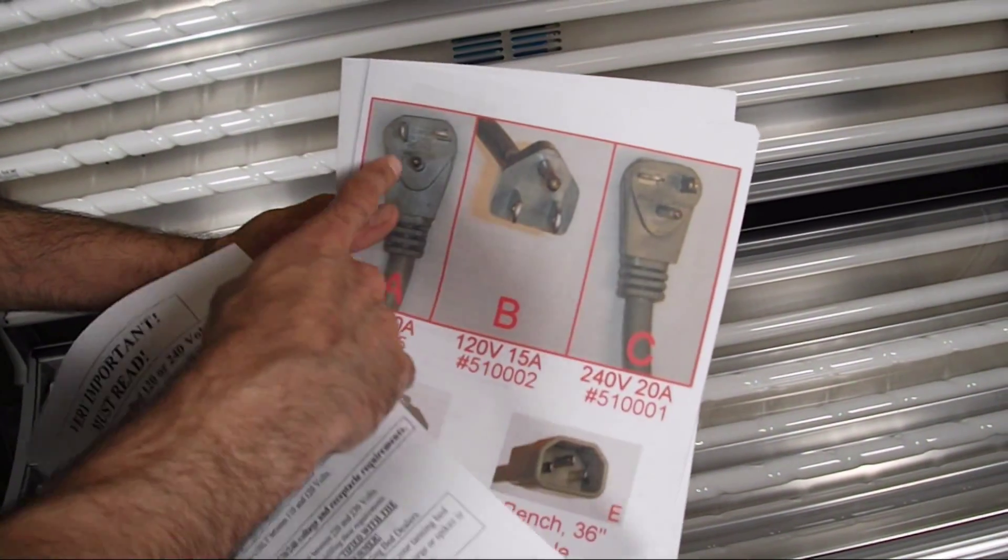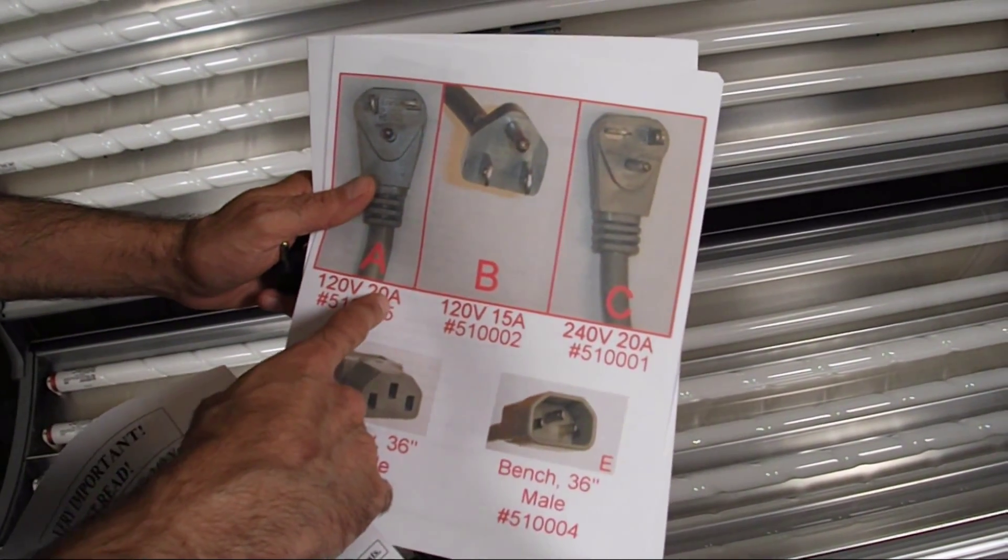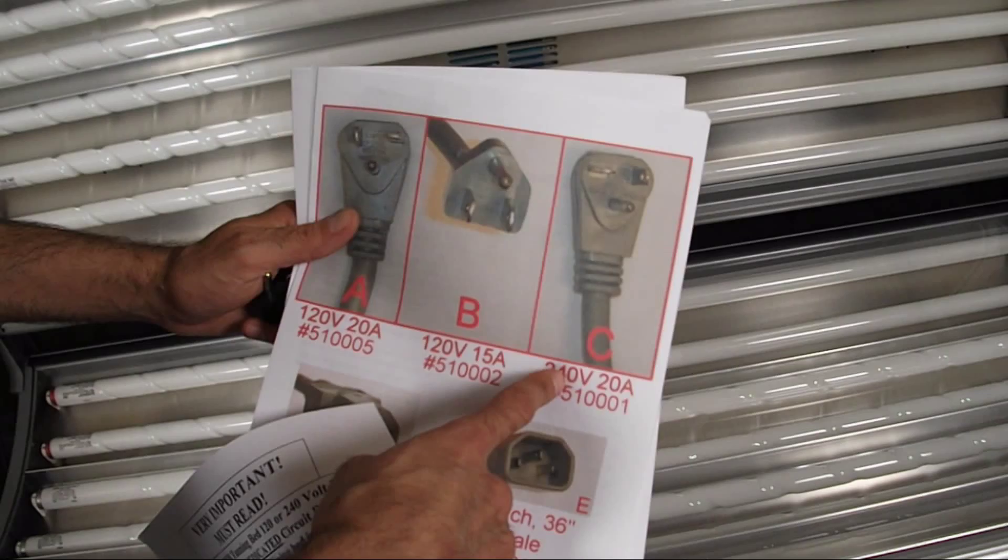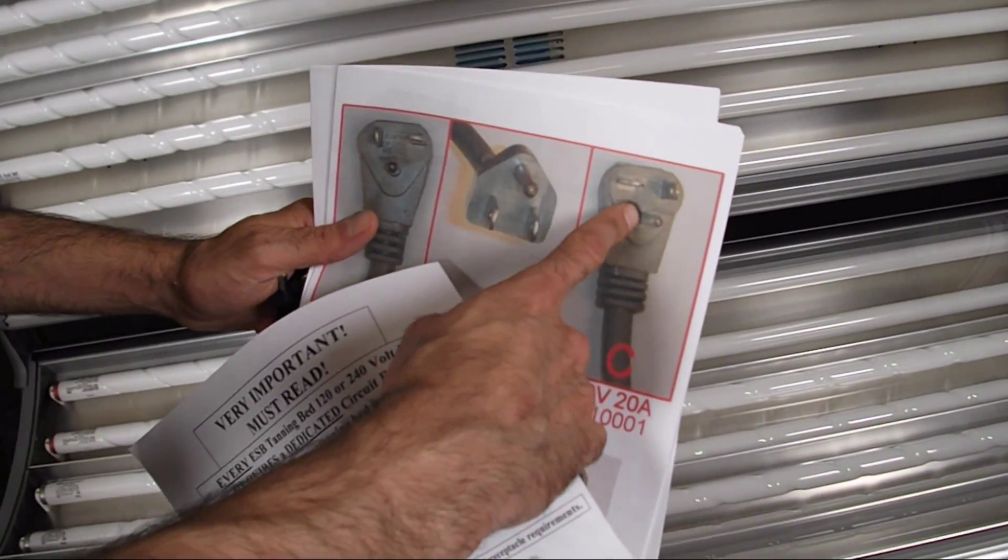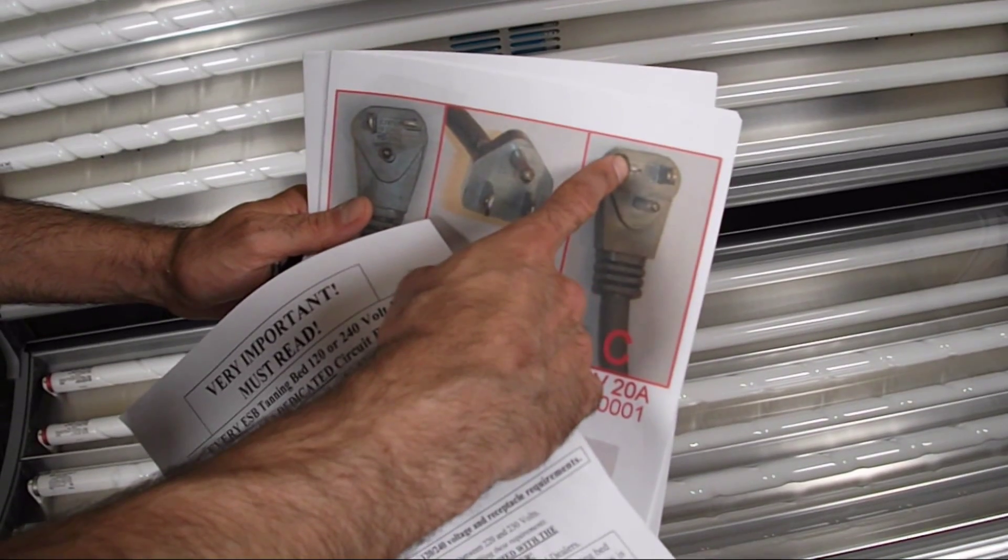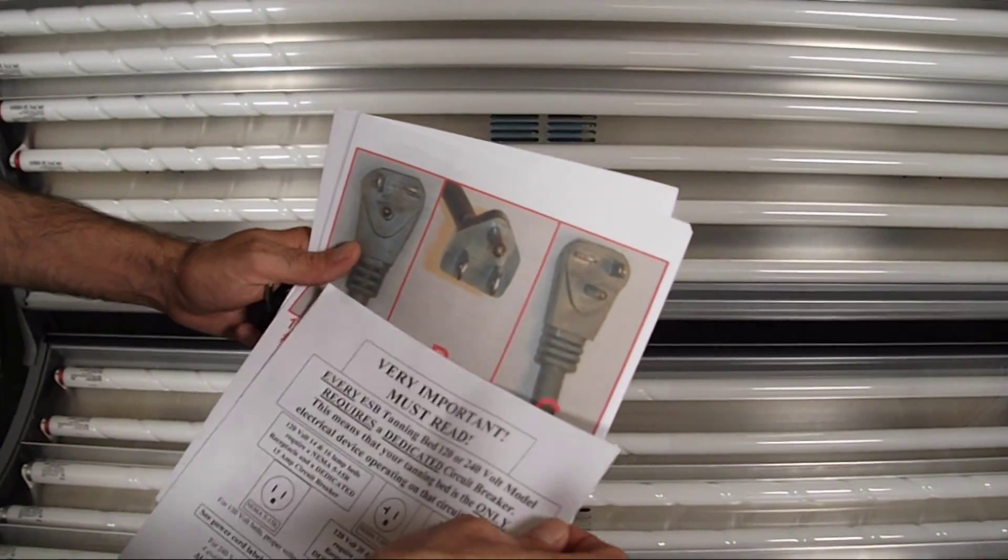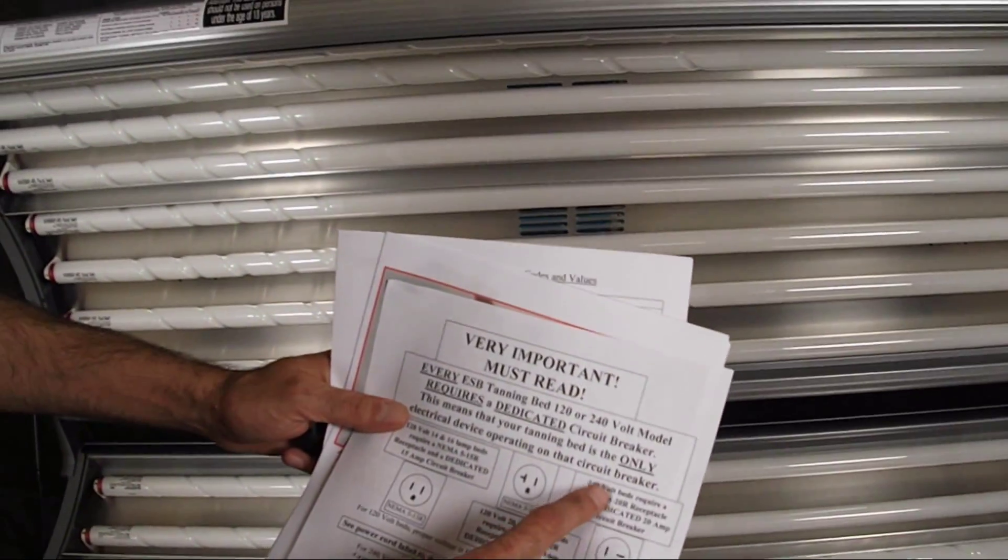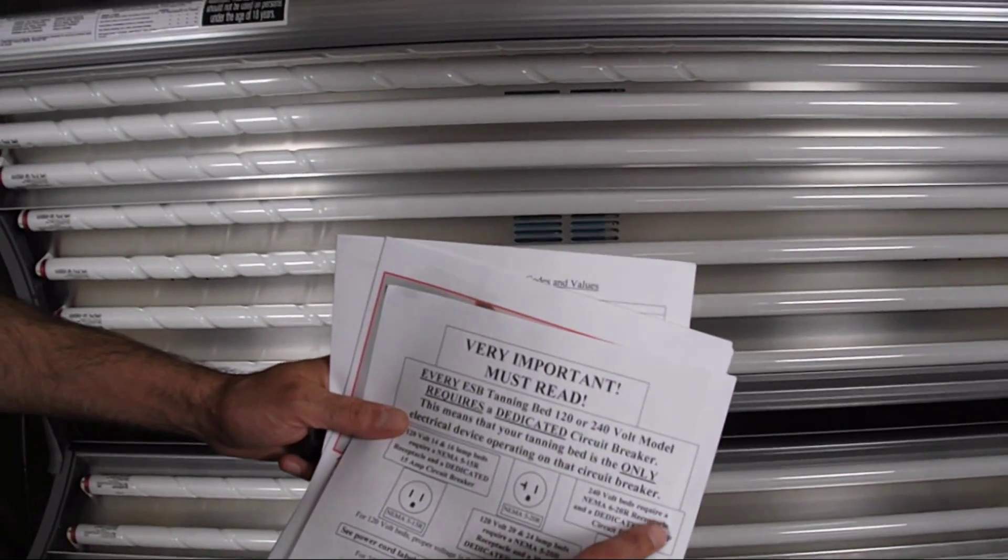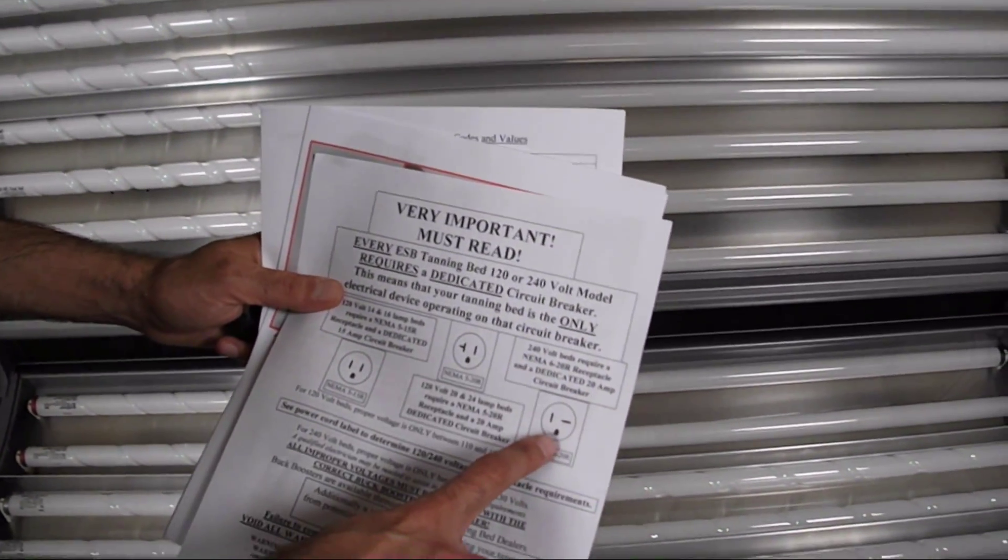This last plug here is actually a mirror image of the 120 volt, 20 amp. This is the 240 volt, 20 amp plug. It has a horizontal terminal on the left and a vertical on the right when you have the ground at the bottom and facing you. So that is for the 240 volt beds. That is the NEMA 6-20R receptacle.